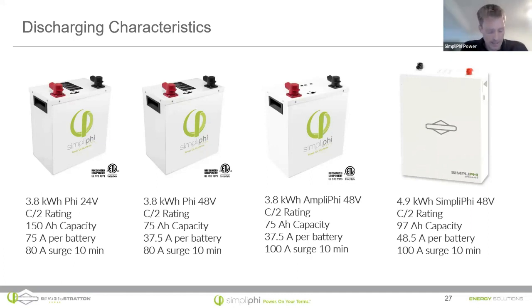The other thing to say is that it's still thousands of cycles, 3,000 plus cycles, taking the battery all the way down to 0%. So occasionally dropping that battery to a 0% state of charge is going to have very little impact on it. But doing that every day repeatedly for a long time can damage the cells. So it's kind of a gray area.